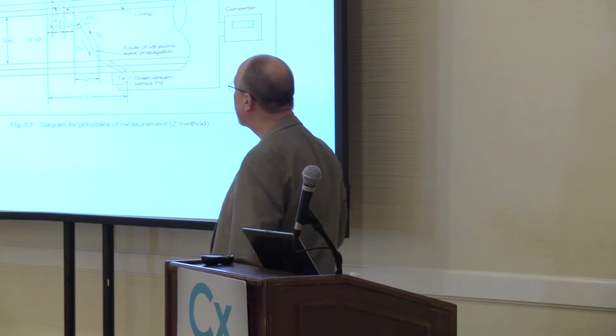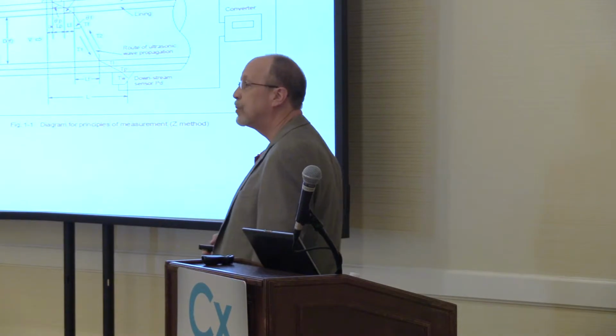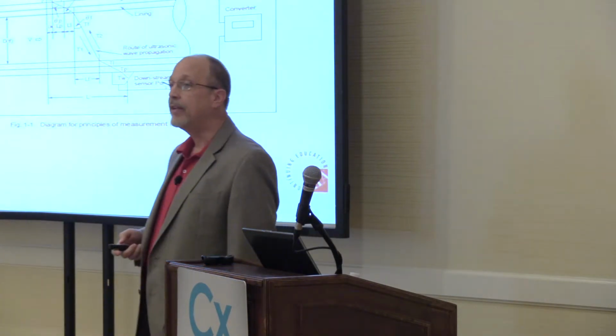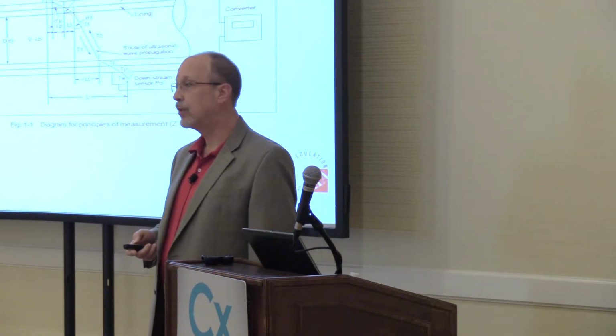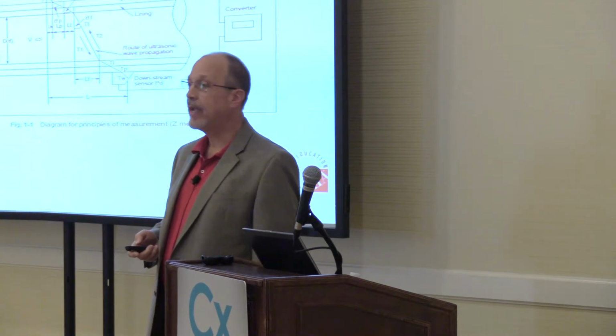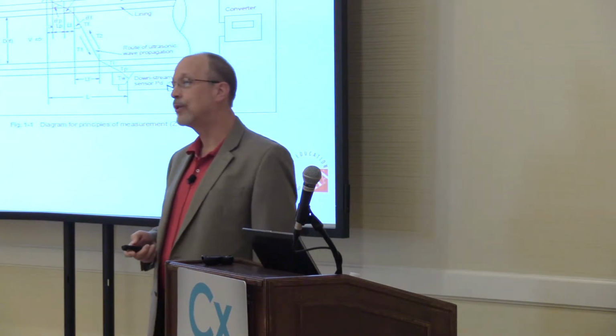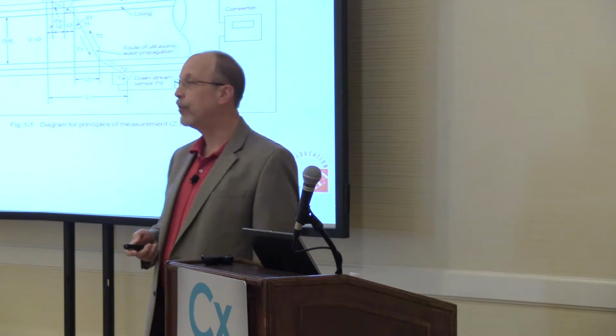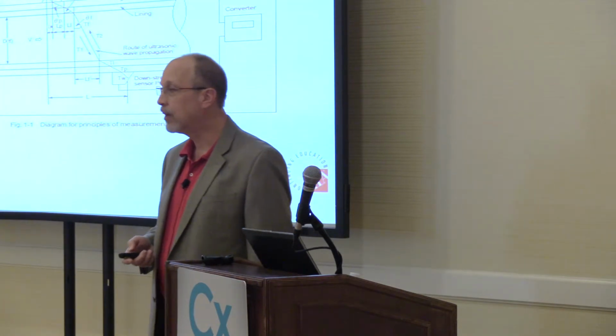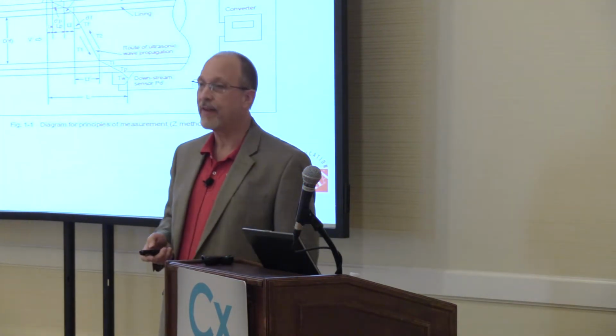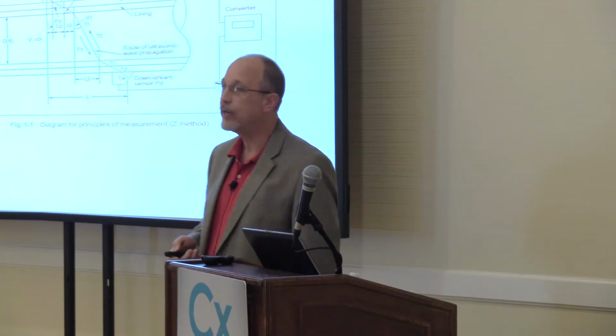In this case, we have a transducer, and the crystal inside the transducer is at a specific angle. It differs between manufacturers in what that angle is. So you can't use a Dynasonics transducer with a GE flow meter. You can't use a Fuji flow meter with a Flexim flow meter, because everybody's got their own secret math equation.